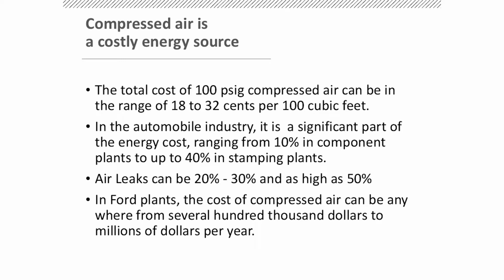So to give you an example, again, 100 PSI compressed air can range anywhere from 18 to 32 cents per 100 cubic feet, depending on if it's an air-cooled system or a water-cooled system. The automobile industry can go anywhere from 10% up to 40% of their actual usage in stamping plants. Air leaks can account for 20 to 30%, as high as 50% of all of the usage. And in four Ford plants that I was at, they can be anywhere from several hundred thousand dollars to millions of dollars in a plant itself, okay?